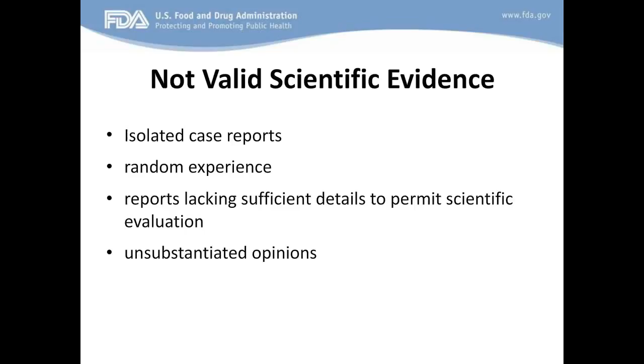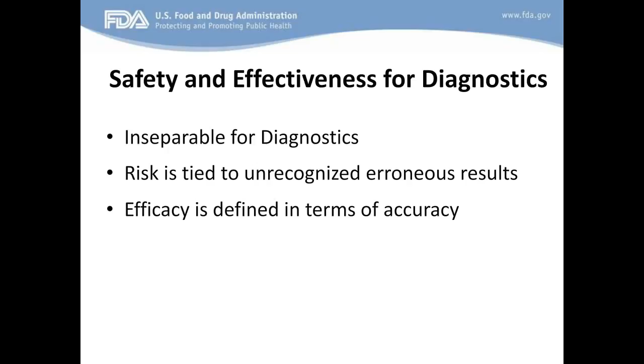Now, based on safety and effectiveness, you might be saying, well, how do safety and effectiveness relate to in vitro diagnostics? It's hard to see safety being an issue with a test that is typically done on samples that are not necessarily invasive, and how does that affect the safety of a patient? Well, we consider both the safety and effectiveness of diagnostics, which are in some ways inseparable for diagnostics. Really, what safety and effectiveness mean is what happens to the patient, the risk to the patient with unrecognized erroneous results. That is, if a test provides a false result, either positive or negative, what is the consequence of that false result to the patient? That's what we consider to be the safety and effectiveness as we look at in vitro diagnostics.